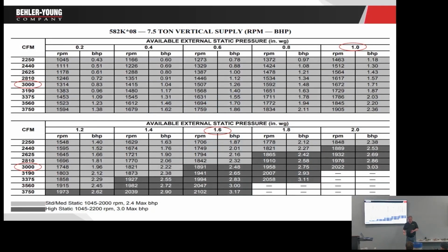Okay. With the old belt drive, generally I can change the motor to go to a bigger motor. Okay. With these, it's a little tougher. Some of them, I would have to change the entire blower assembly, so I'd have to order all the parts for the high static unit. Okay, but this is a great tool when you're trying to measure airflow. Because if you're not getting the airflow you're supposed to, and you got this thing set up to 10, I still can't get the airflow, this document here would tell me my medium static unit is not capable of running against 1.6 inches, right? So I may have to do something to this duct system to reduce the static.